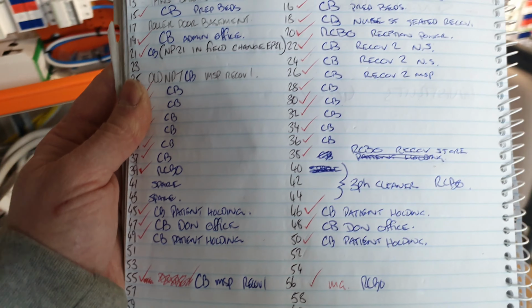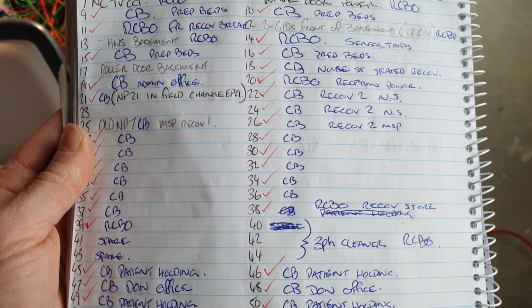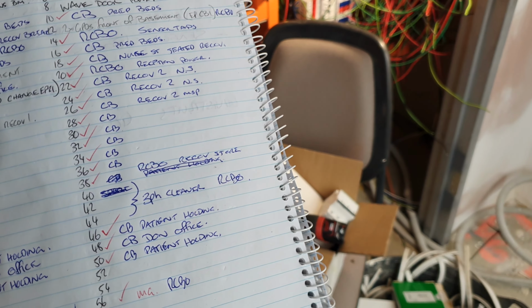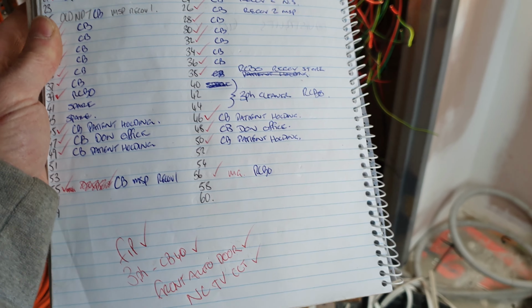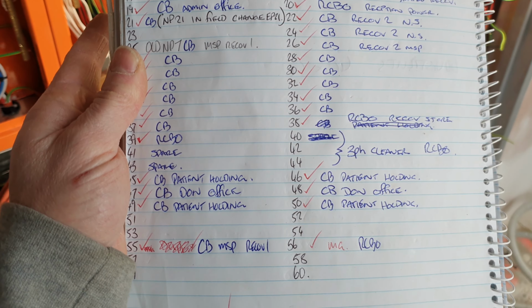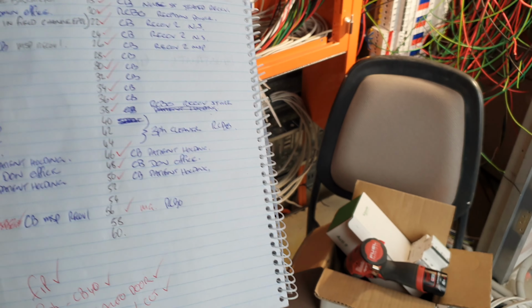I have to put a circuit breaker in the board, because you can't have 2 RCDs. Because if you had a 30 milliamp RCD and a 10 milliamp RCD in the field, and the field one didn't trip but this one did, you'd have a staff member coming back to the switchboard to reset a breaker.